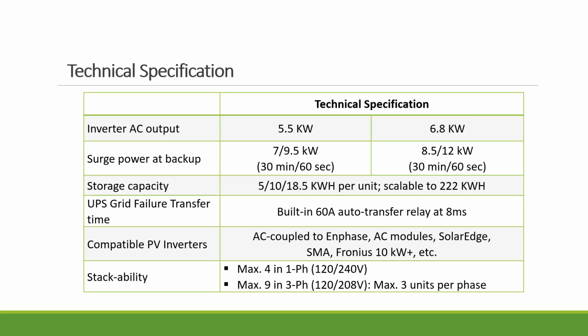Here are some technical specifications. These days, when you look at an inverter, it's very important to look at the AC output at full capacity and also the surge capacity, because you need that to design how big a critical load panel or essential panel you want, and, based on your inverter and your load panel, to design the battery bank as well. Again, we're going to talk about that in the design and installation webinar. It has a built-in transfer relay, so you do not need a separate transfer switch, but with big systems of 3 or more stacked, you might need an external transfer switch. With 1 or 2 units, it's not necessary.